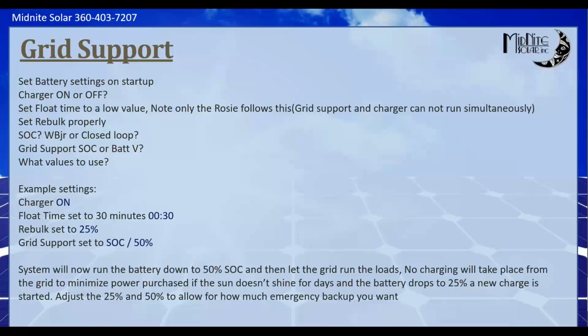If you could watch it, there are about 20 spots where it migrates back and forth. What I mean is at 50.9% state of charge, all your loads are coming from the Rosie. At 50.8%, Rosie starts kicking back a little and using some of the grid. Then as it drops below 50%, at 49.9%, all your loads come from the grid. So right at that teeter point of 50.0, the Rosie will basically balance and try to stay there.